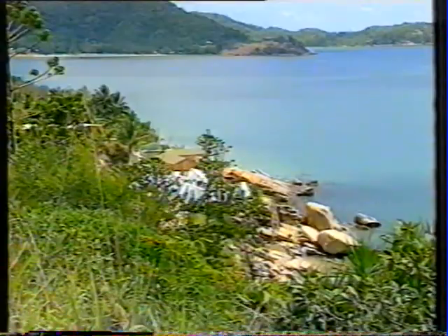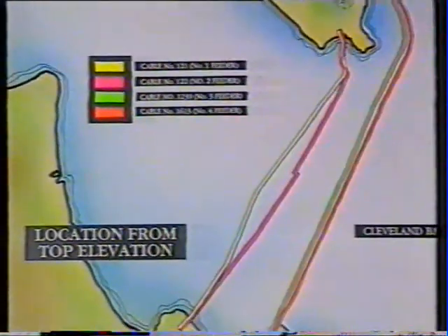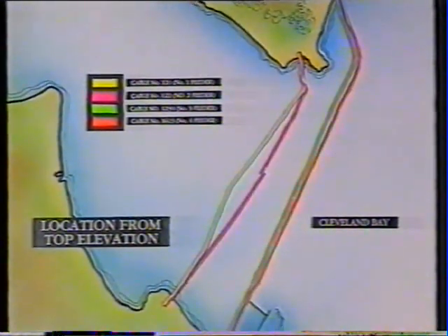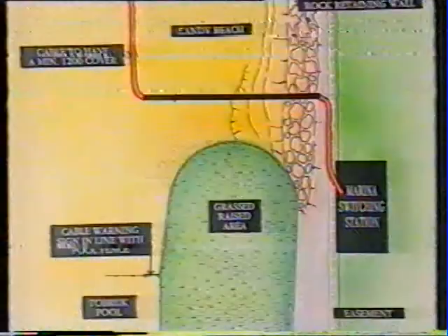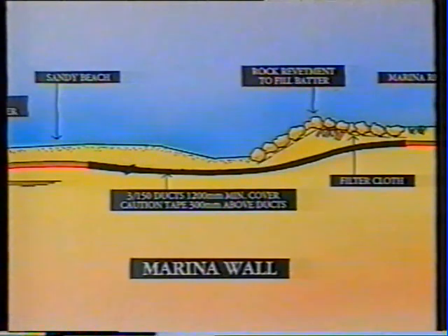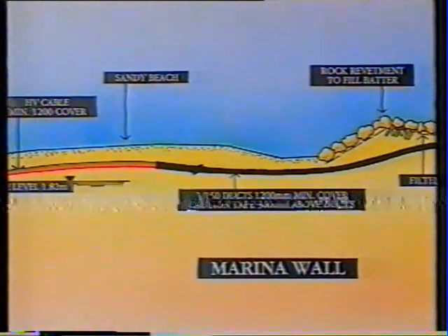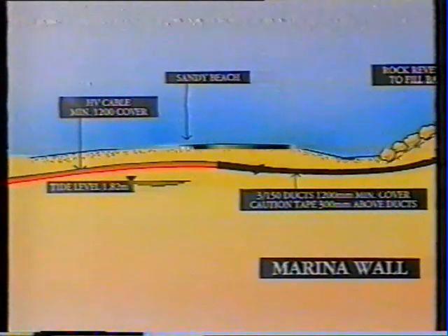Magnetic Island is a relaxed tourist environment, patronised by most visitors in the region. This influx of tourists further increases the demand for suitable accommodation and facilities. Currently, the island is supplied with power from 3 submarine cables with a firm capacity of 2 MVA. With this additional cable, the firm rating to the island is now increased to 7 MVA. The cable route commences at the mainland marina switching station and goes under the marina seawall, along the beach and into the water, where it will be buried out to the end of the marina entrance channel, crossing an existing telecom cable on the way.